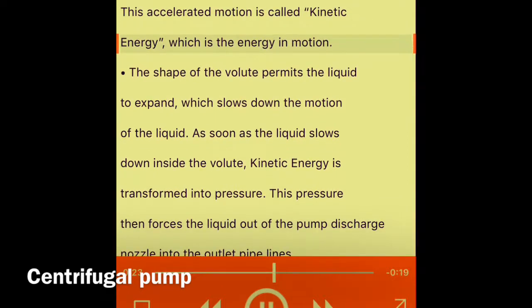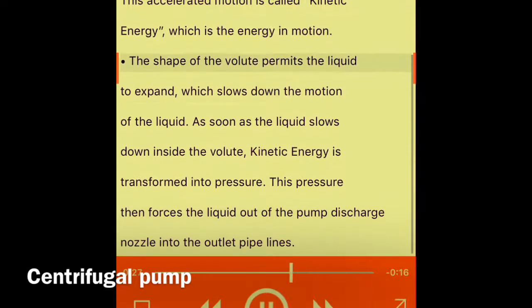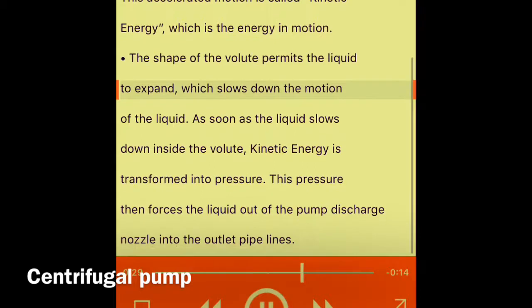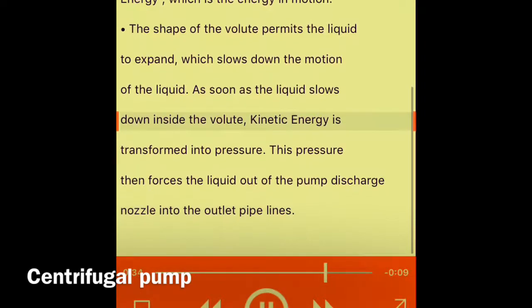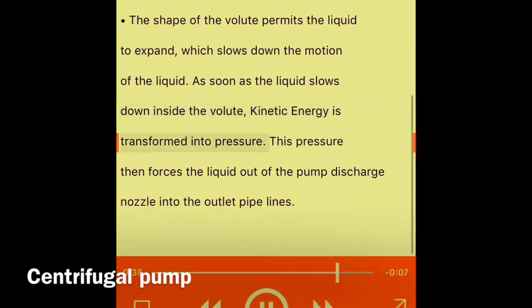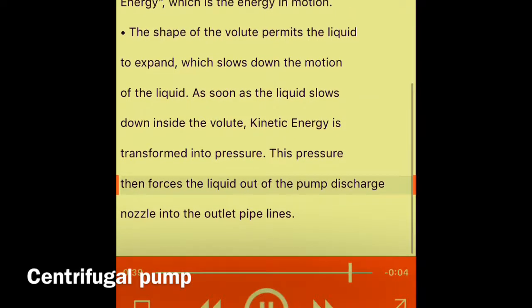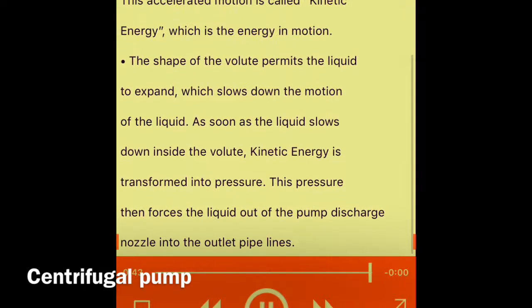Kinetic energy is the energy in motion. The shape of the volute permits the liquid to expand, which slows down the motion of the liquid. As soon as the liquid slows down inside the volute, kinetic energy is transformed into pressure. This pressure then forces the liquid out of the pump discharge nozzle into the outlet pipelines.